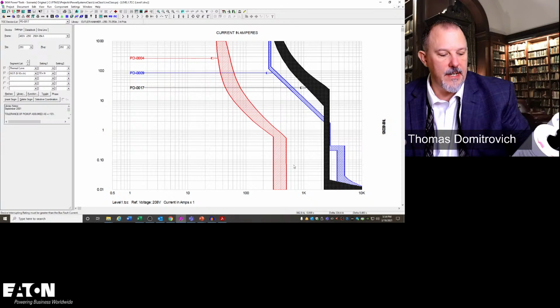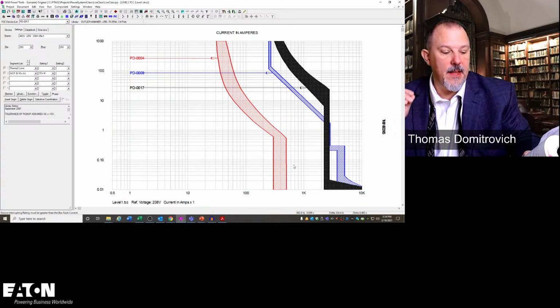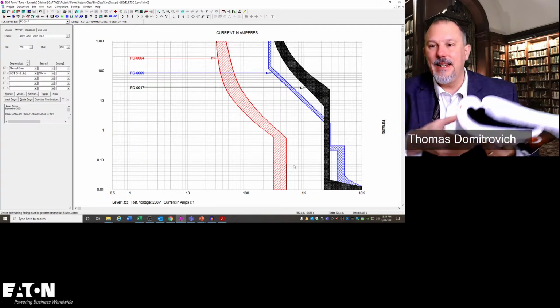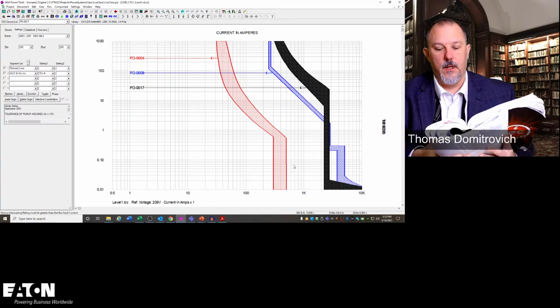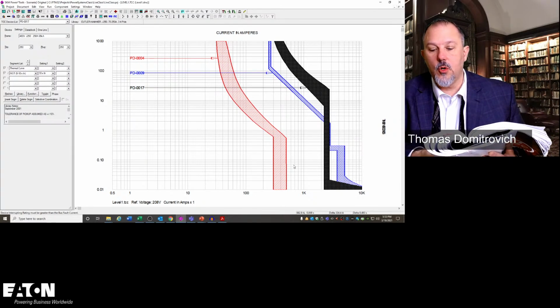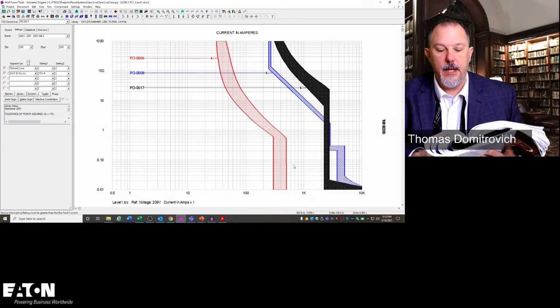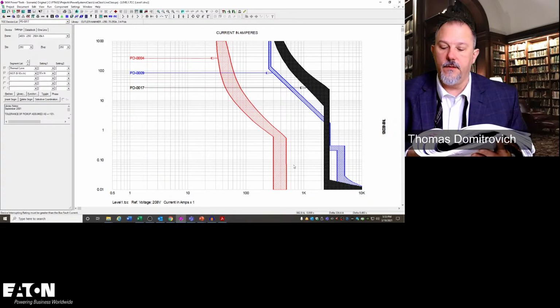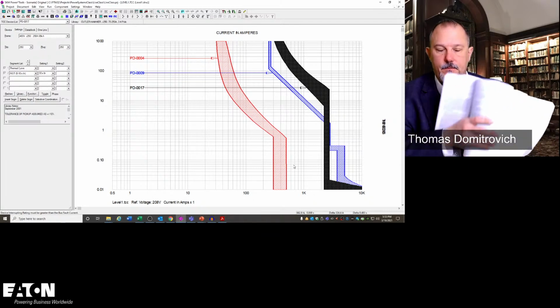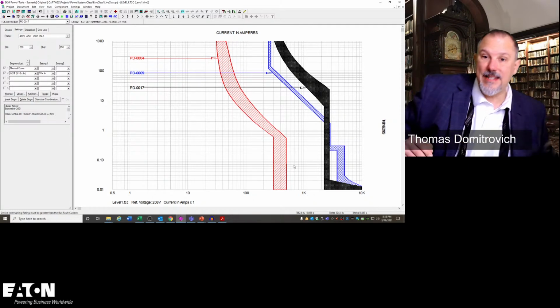Overcurrent protective devices serving the essential electrical system shall be coordinated for the period of time that a fault's duration extends beyond 0.1 seconds. And it says in an informational note that the terms coordination and coordinated as used in this section do not cover the full range of overcurrent conditions. So what does that mean?